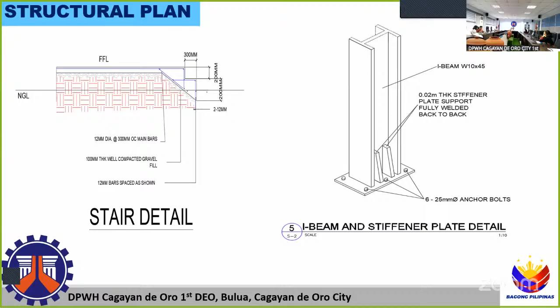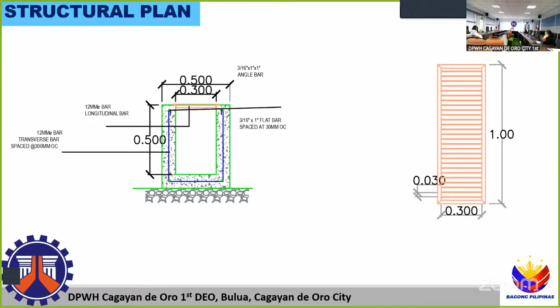For our line canal, we have a width of 0.50 with a clear width of 0.30 meters and a depth of 0.5 meters. For the removable cover, we will use an angle bar 1 by 1 by 3/16 thickness with a width of 0.3 and a length of 1 meter.